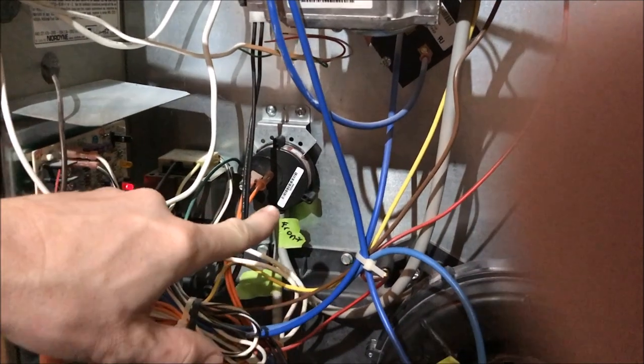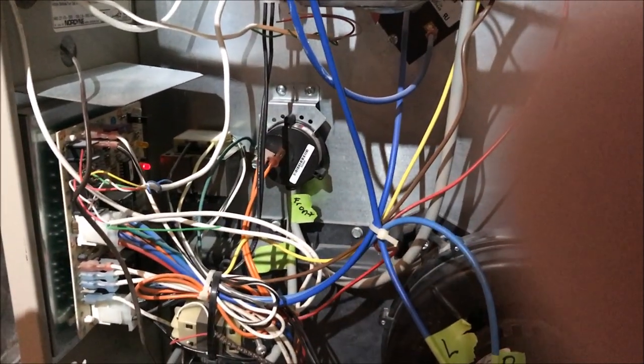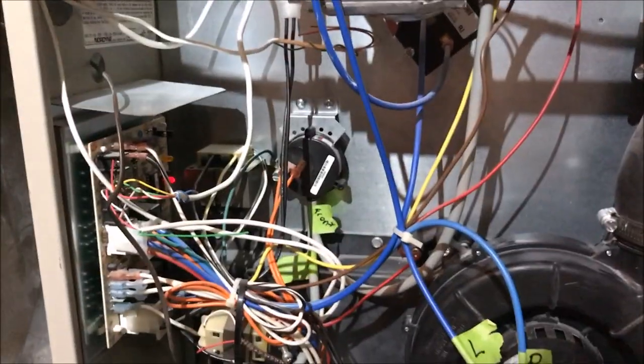It's the error code that indicates the pressure switch is reading closed. So it's not necessarily a problem with the pressure switch but more than likely a condensation built up in your p-trap down there. I'm going to give you the proper procedure for clearing your p-trap and making sure some other things aren't plugged up before you try to turn it on.